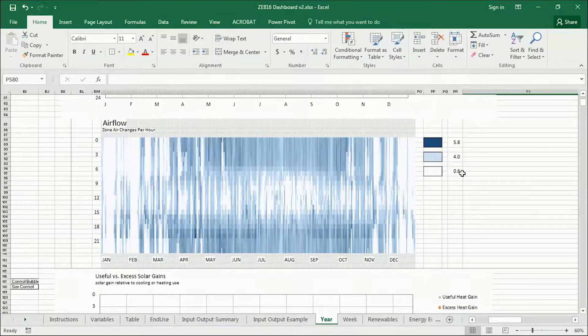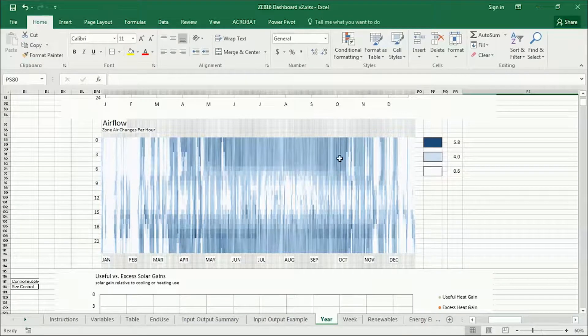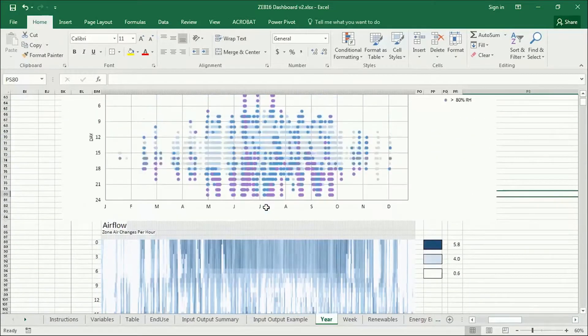A baseline — the minimum when it's white — is at 0.6, which just represents the infiltration plus fresh air. There's a lot of ventilation going on in the morning and in the nighttime, and not so much in the midday. That's probably because the outdoor temperatures are higher than the indoor temperatures.